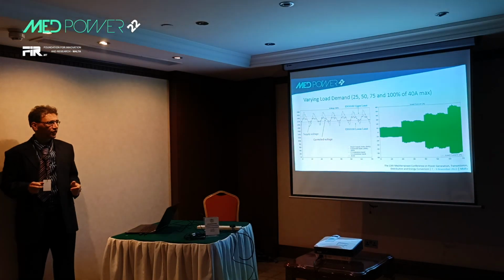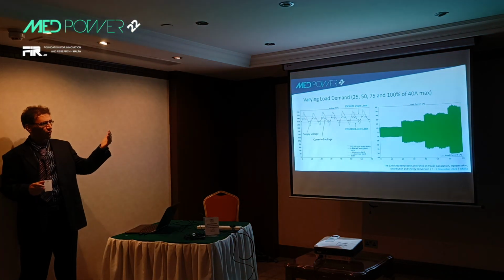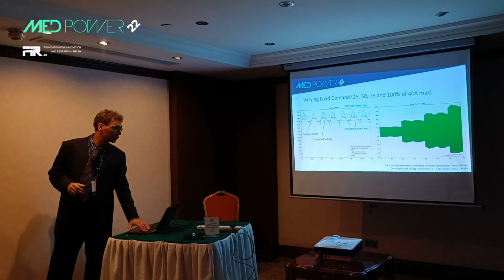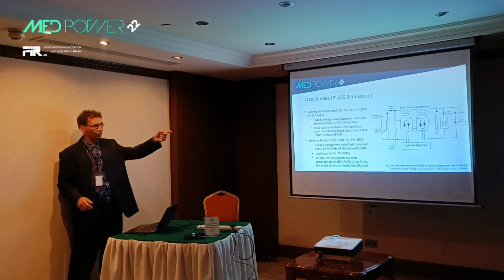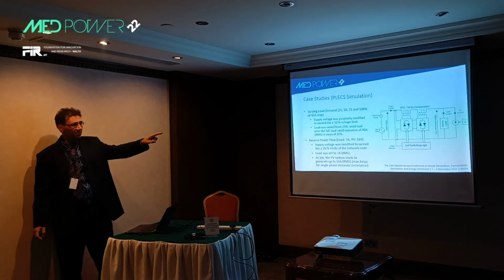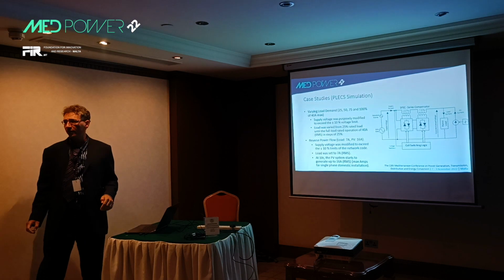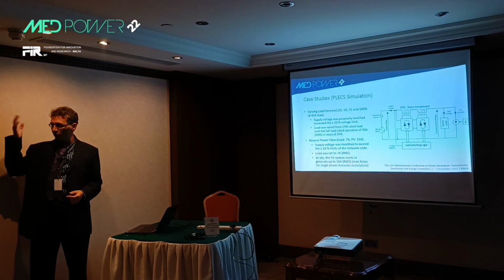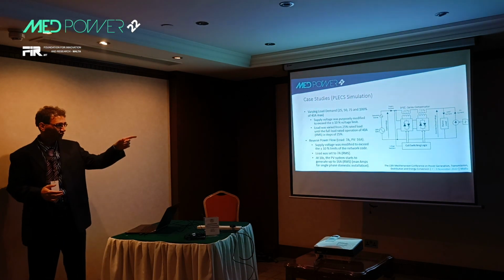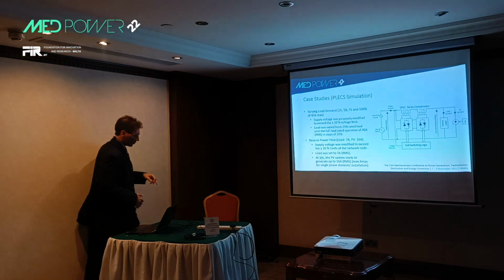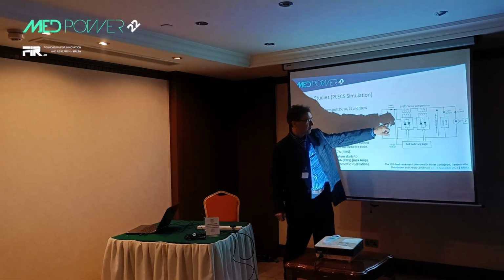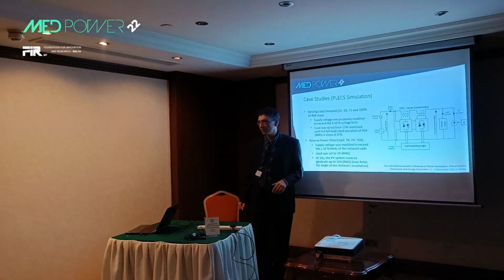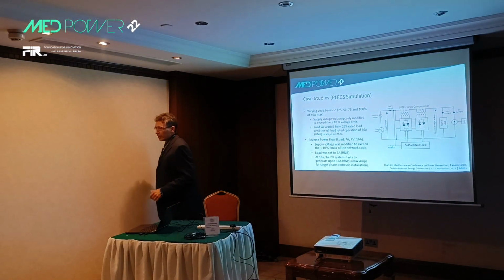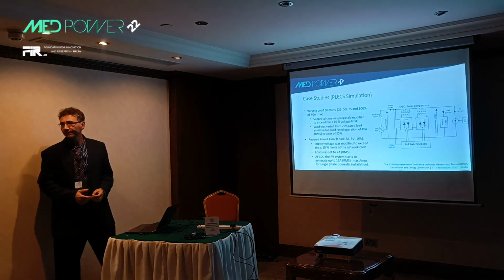And in terms of harmonics, the thyristors are not going to be switching all the time, and they are going to be switching on the low current side. So the harmonics that will be generated are extremely negligible. If you are thinking about harmonics caused by thyristors, you can see the thyristors are on the low voltage side of the coil, so they are going to be nearly non-existent. Okay. Thank you very much.